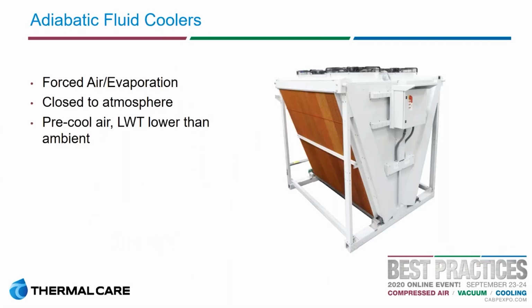The next type of cooling for a high temperature, so not using refrigeration, is an adiabatic fluid cooler. What this does is combine a traditional dry fluid cooler, which is essentially like a radiator on your car, using forced air to cool a liquid, with an adiabatic process that pre-cools the air. If you see on that unit depicted, the brownish red area on the side is a medium that can be soaked in water.